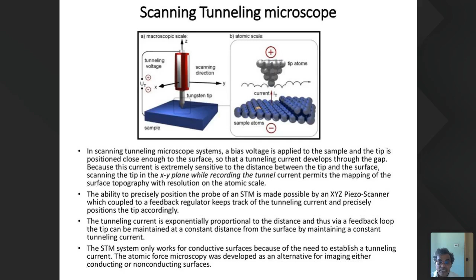The ability to precisely position the probe in an STM is made possible by an XYZ piezo scanner, which, coupled to a feedback regulator, keeps track of the tunneling current and precisely positions the tip accordingly. The tunneling current is exponentially proportional to the distance, and thus, by a feedback loop, the tip can be maintained at a constant distance from the surface by maintaining a constant tunneling current. The STM system only works for conductive surfaces, because establishing a tunneling current requires a conductive sample.